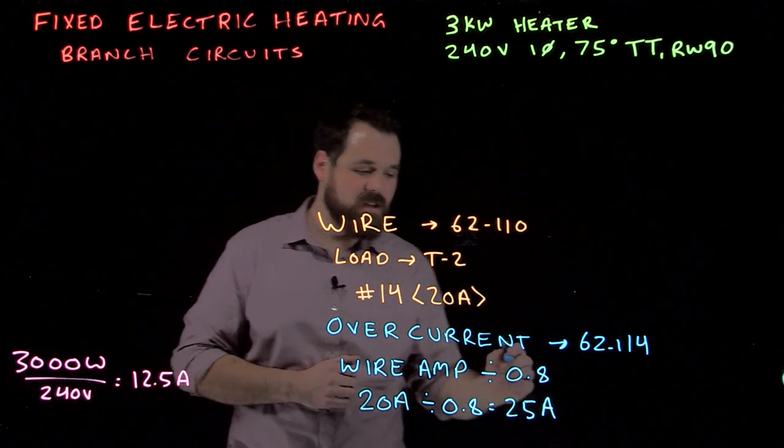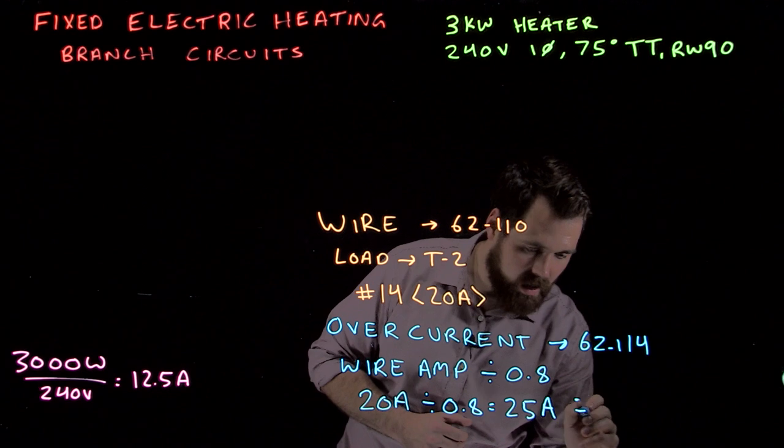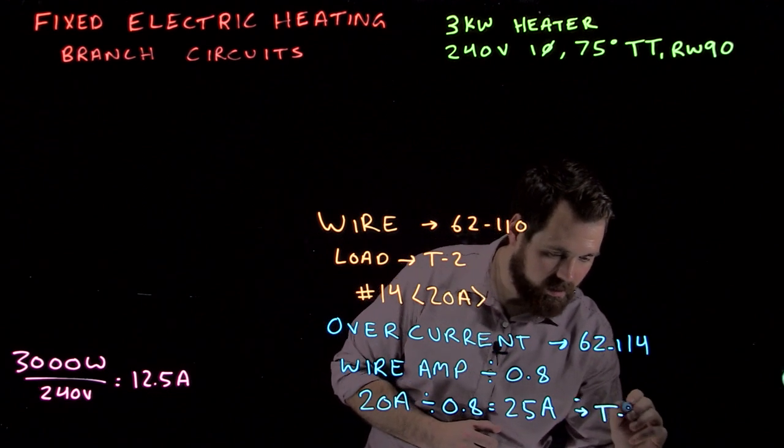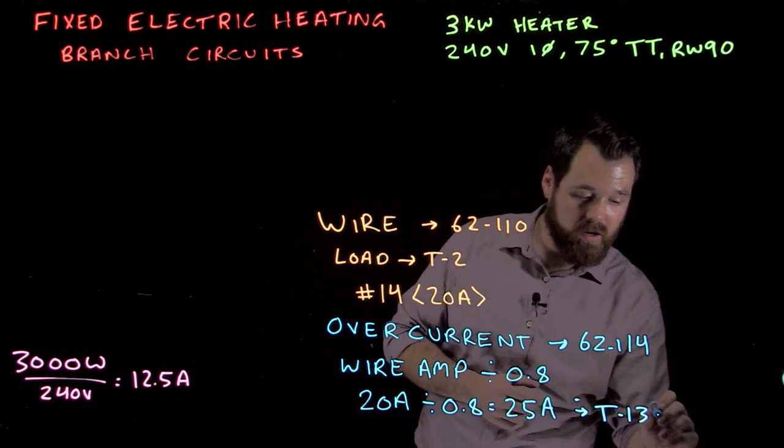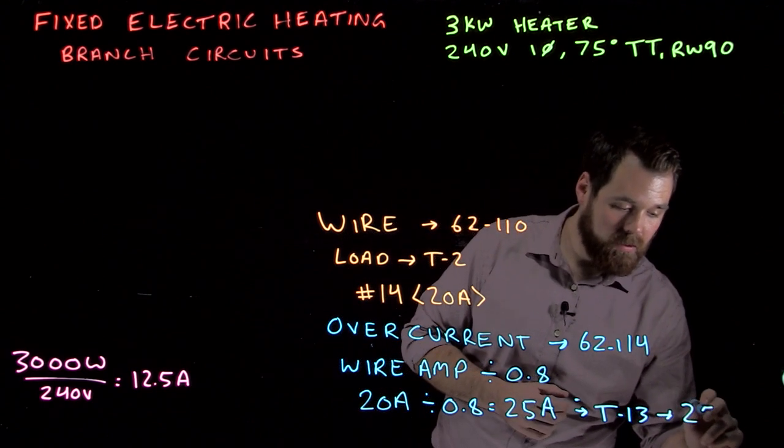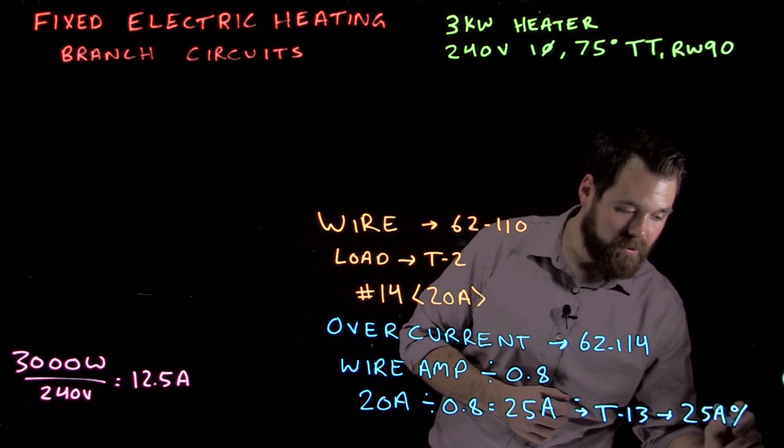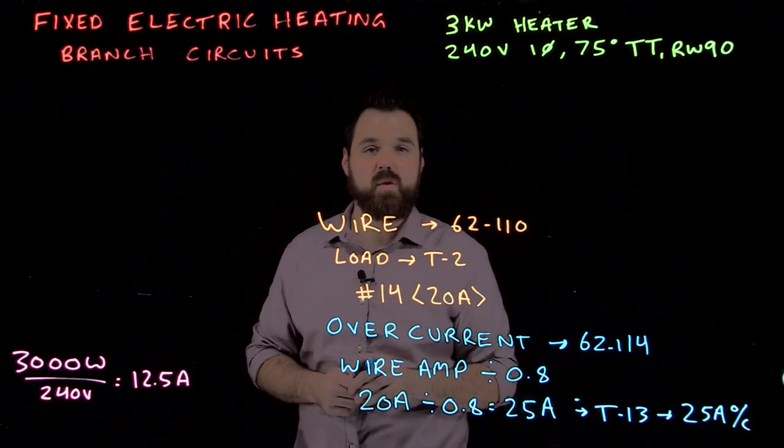We are going to take this number and we take that number to table 13. Luckily for us, there is a 25 amp breaker available on table 13, so we get a 25 amp overcurrent.